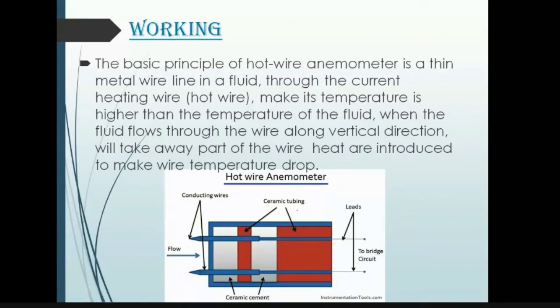Now we will see the working of the hot wire anemometer. It works when an electrically heated wire is placed in a flowing gas stream, and the heat is transferred from the wire to the gas, making the temperature of the wire reduce, and due to this the resistance of the wire also changes. This change in resistance of the wire becomes a measure of flow rate. And then we will see the applications slide.